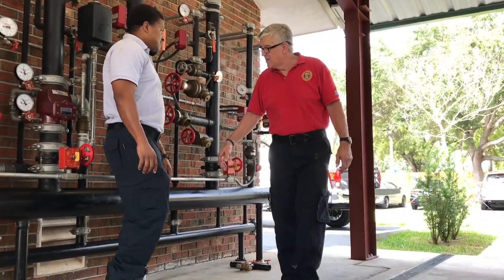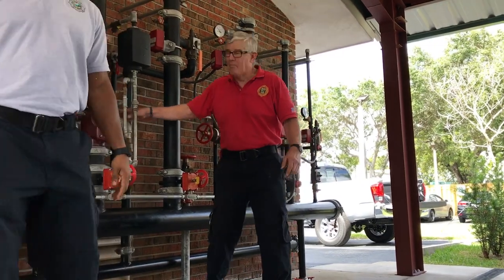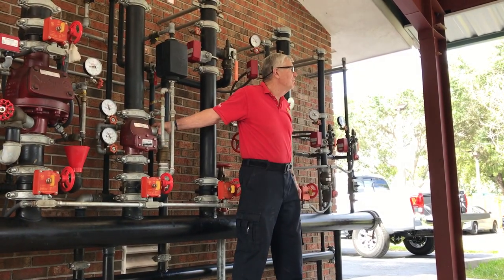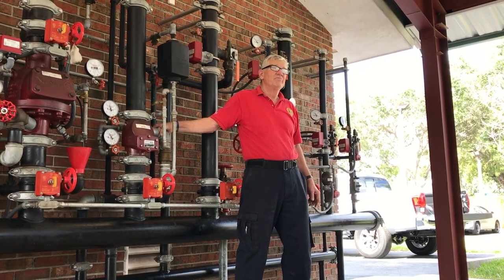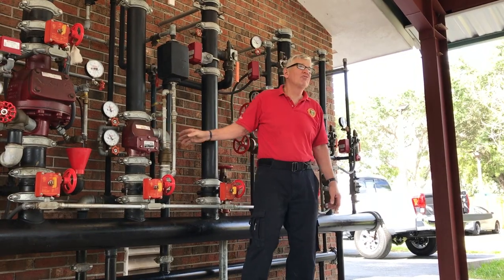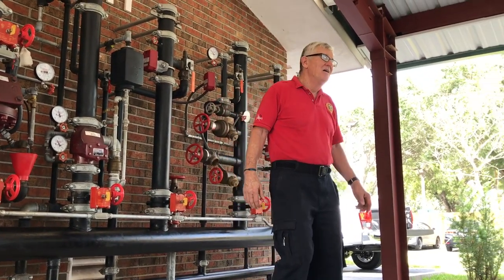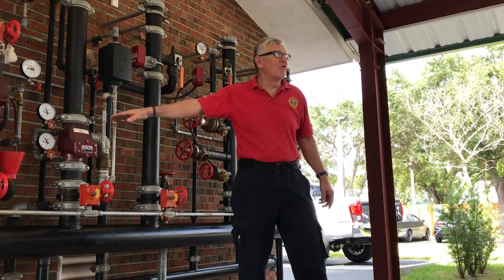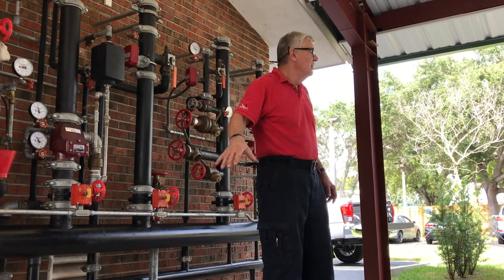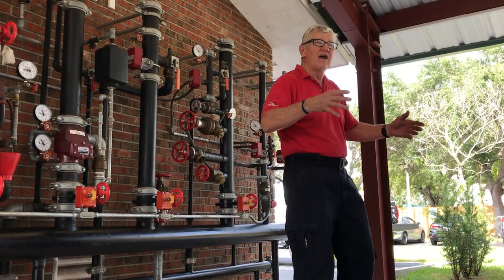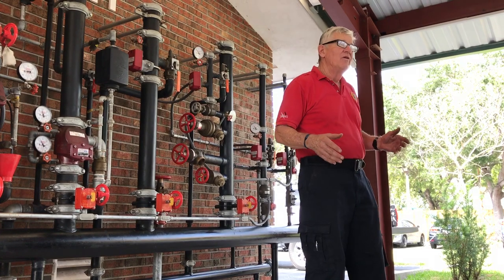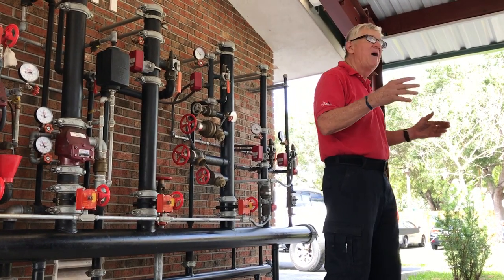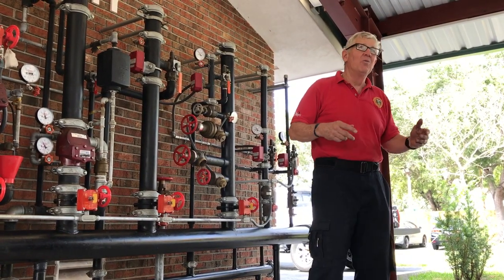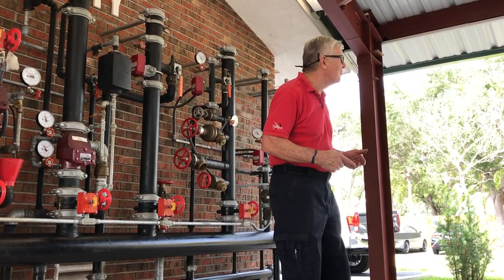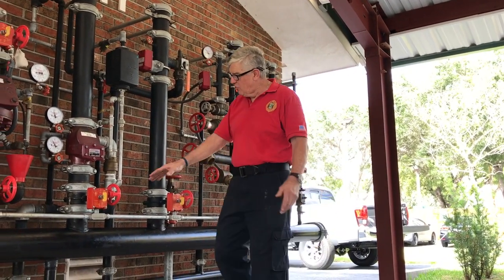Now, thank you, Mark. This is one of my favorite sprinkler installations because it's old school, just like me. This has been around for well over 100 years. This is before you had electric alarms. You had an alarm that was powered by water. It's almost like a fire pump in reverse. So you have a control valve.